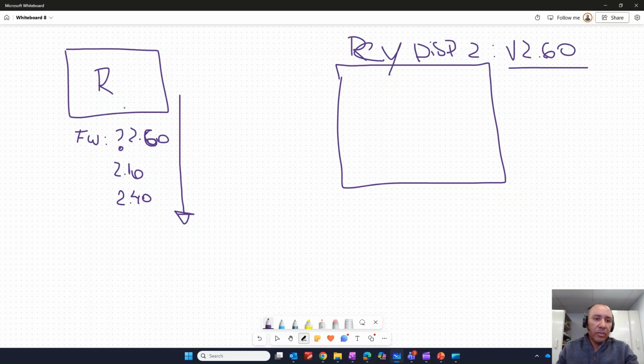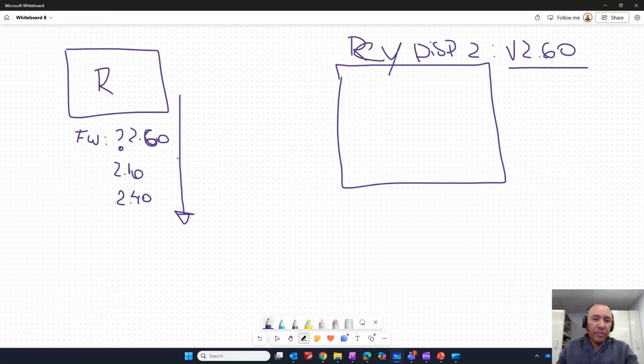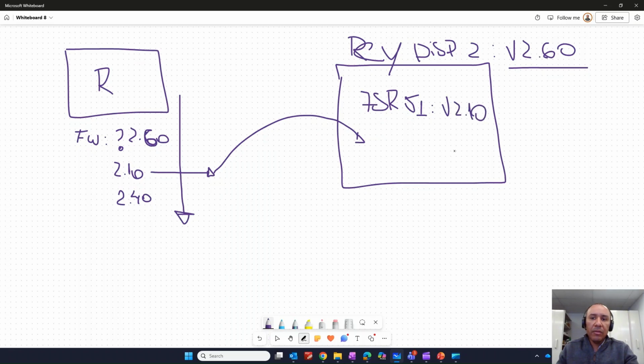Let's assume that your device has firmware 2.10, as I mentioned, and you need to get this template here, 2.10. After you get this file, you need to import it inside of Reyrolle Manager, so that you can have the software running on 2.60, but configure the relay 7SR51 on version 2.10.